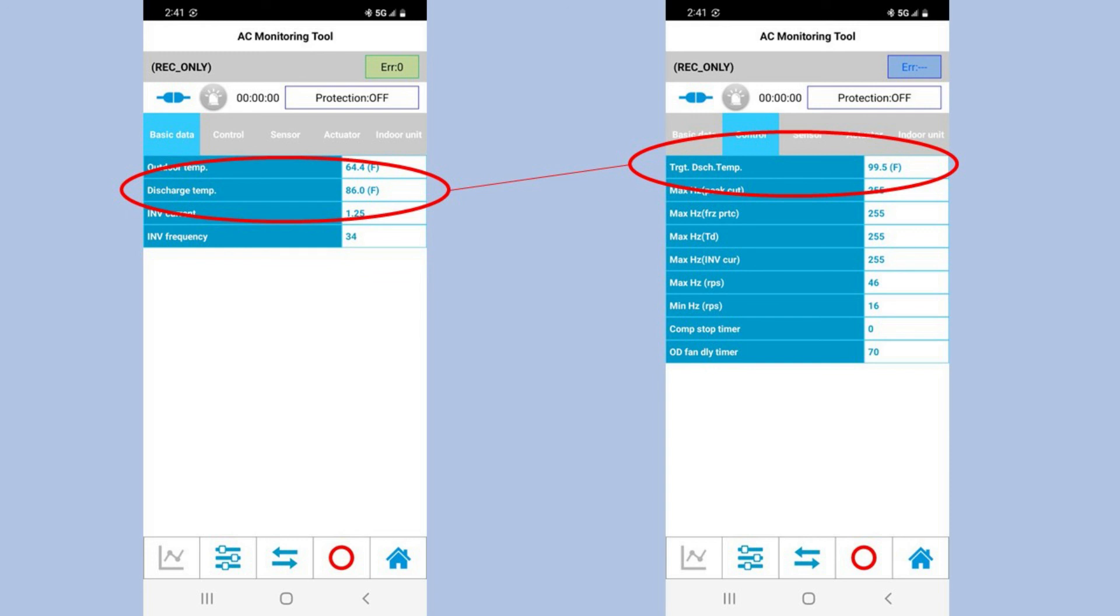On the heating mode, if everything looks good on that coil at 108 to 116 degrees, it's not going to speed the compressor up until we push a little more cold or release a little more heat by speeding the fan up and pulling some heat off that evaporation coil, which would be the condenser during heat pump mode.